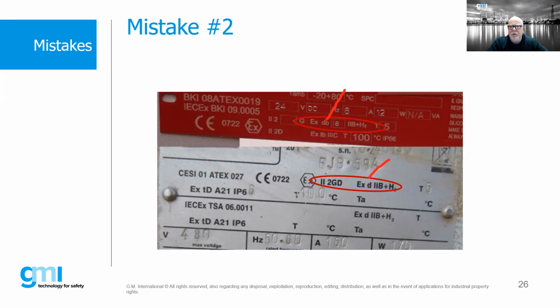However, notice this. We have also IA. What this means is that with this particular enclosure on the top, it's actually a flame-proof enclosure that contains intrinsically safe associated apparatus. On the one below, I don't see an IA. So when I open up that box below and I look inside and I see intrinsically safe associated apparatus providing protection downstream to some devices, I don't see an IA. Guess what? That box is not certified to house intrinsically safe components, as is. So we need to be aware of these little things to make sure that we're aware of all that good stuff.